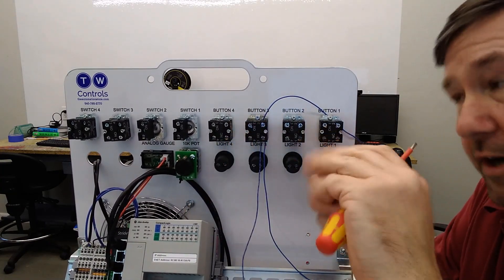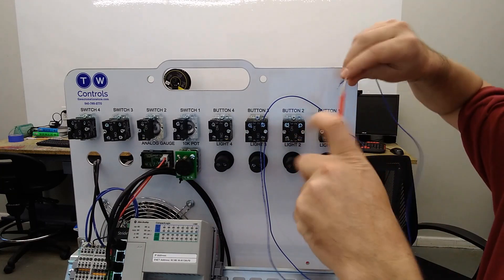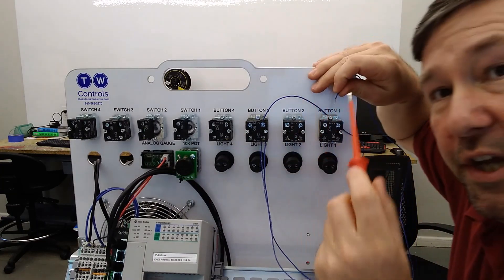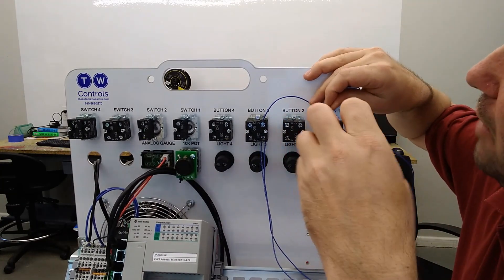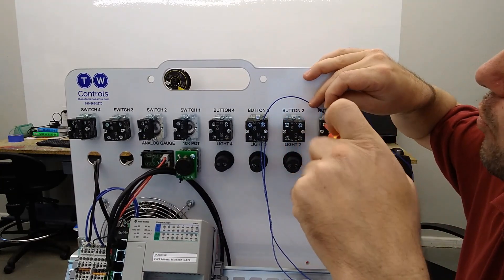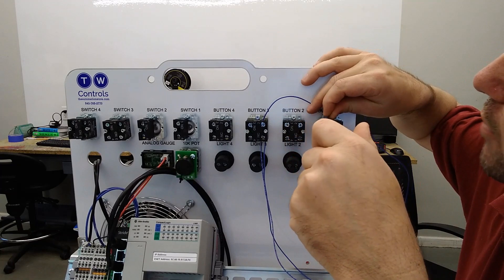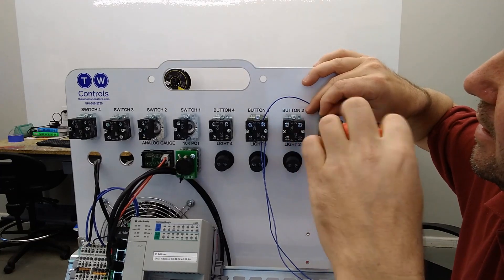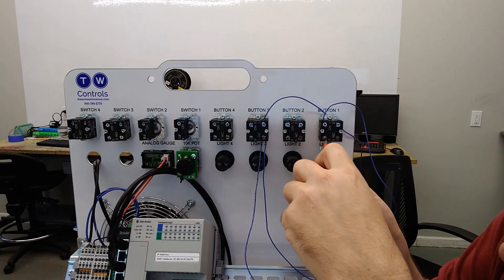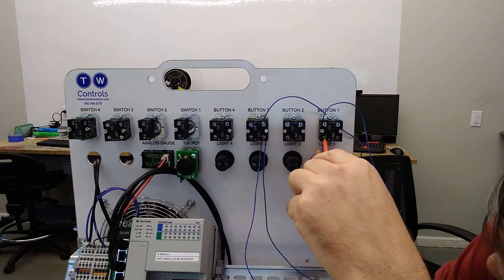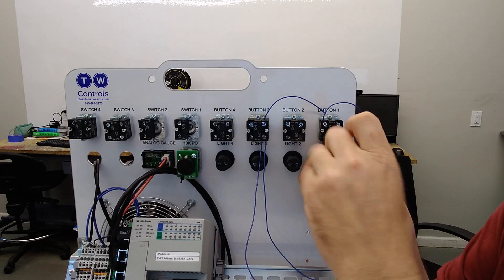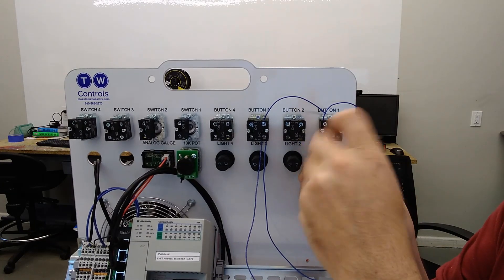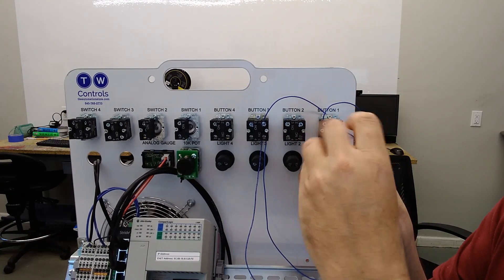And then that jumper wire is going to go to the normally open top of button number 1, our green button. And then terminal 2 is going to go to the bottom of our normally open contact on button 1.